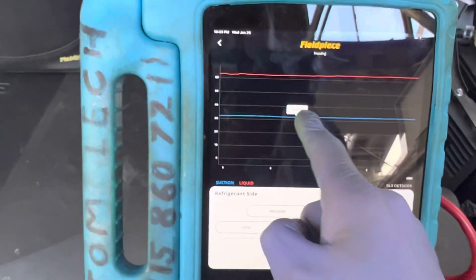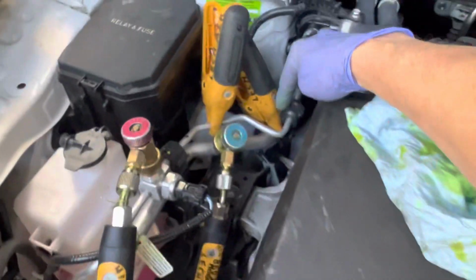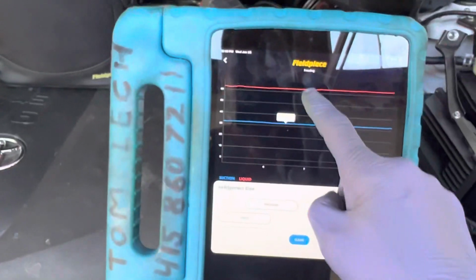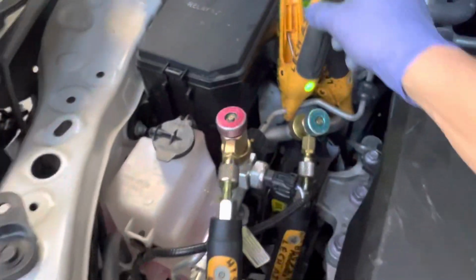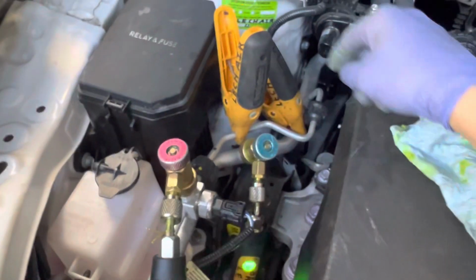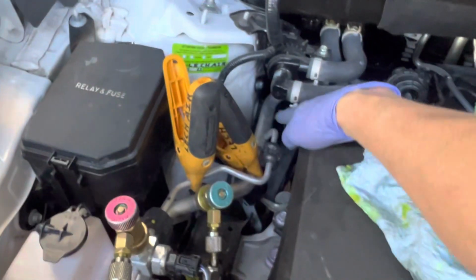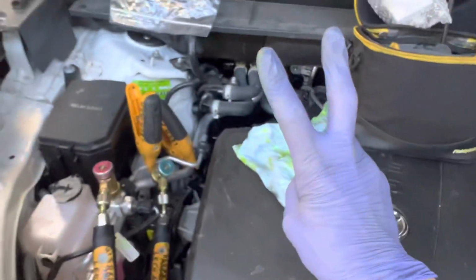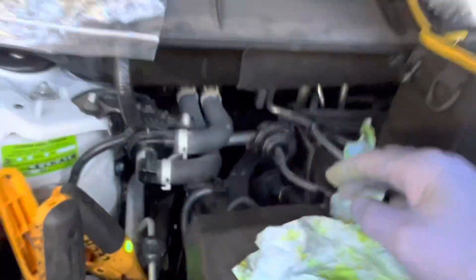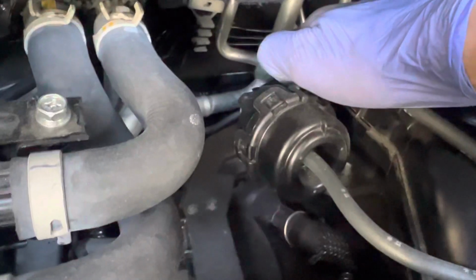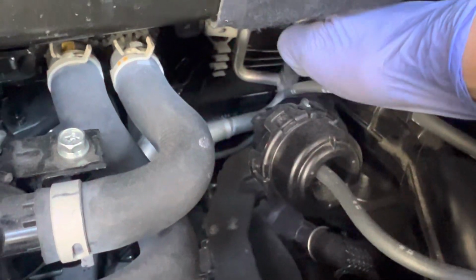We look at our line temperatures. We're at 32.2 degrees at this point right here. We're at 63 degrees at this point on this liquid line. So let's take this 32 degree line. This is after the internal heat exchanger. This is a dual AC system. There's a second evaporator in the back, and you can tell that by that T and that Y right there. That T off is going to the rear evaporator. You can't see that very well, but we're going to tee off on that.